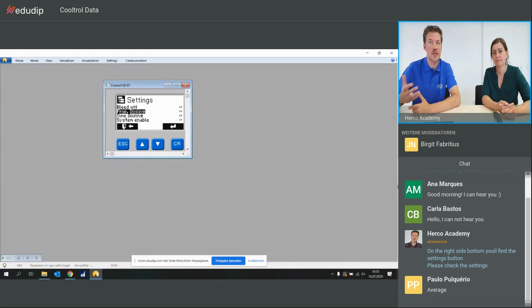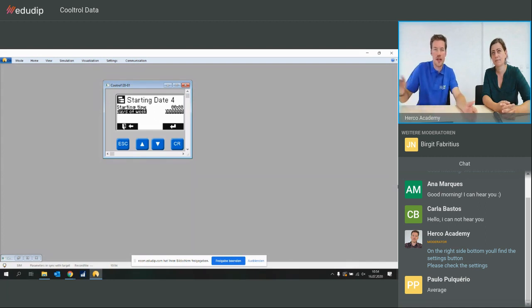and for time dosing, you basically set up when we want to start the biocide. So we go down here, and you see we have 4 different starting times, so we can say we want to do one in the morning, one after lunch, one in the evening, or whatever, and can say when it should start, and then also on which weekday. So we can say, okay, Monday, Wednesday, and Friday we do something different than Tuesday and Thursday. So you're really flexible with this one.